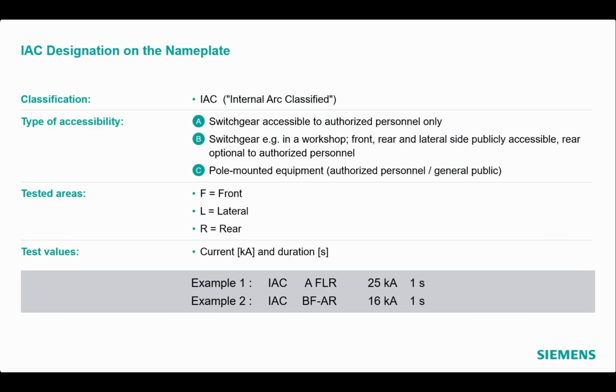IAC designation on the nameplate. Let us investigate what is mentioned in the nameplate of the switchgears which are IAC classified. The classification IAC, as stated previously, stands for Internal Arc Classified. Types of accessibility. The types of accessibility are assigned to the switchgear after meeting the requirements stipulated in the IEC standards concerning test procedures and personal safety.